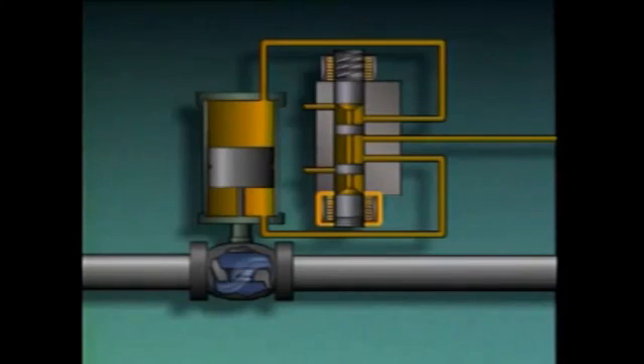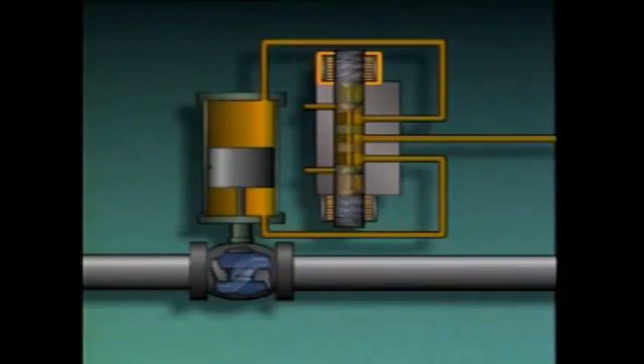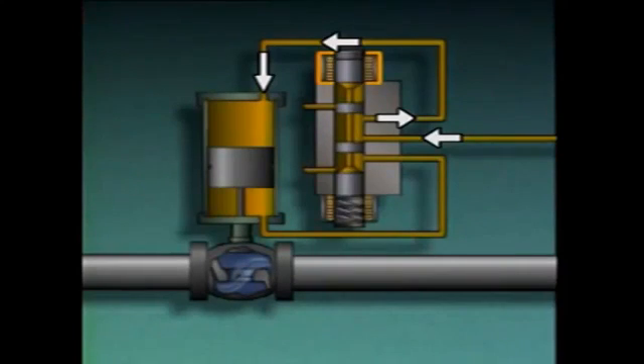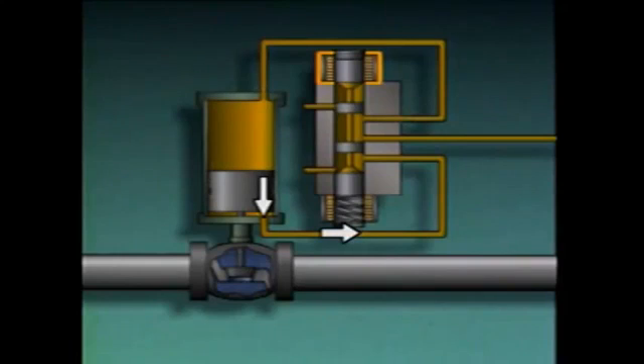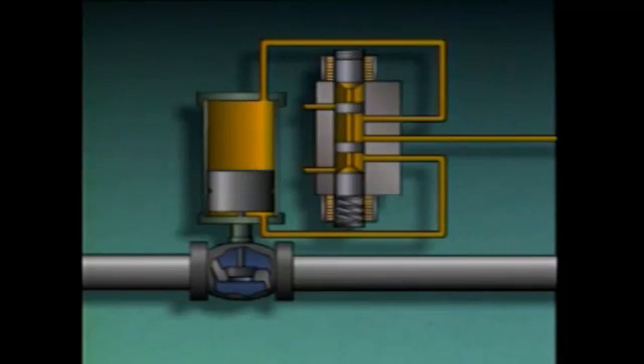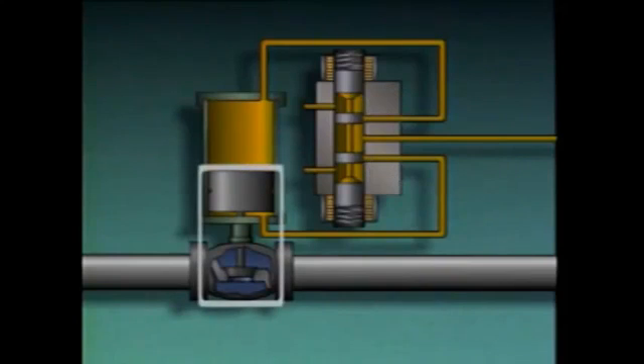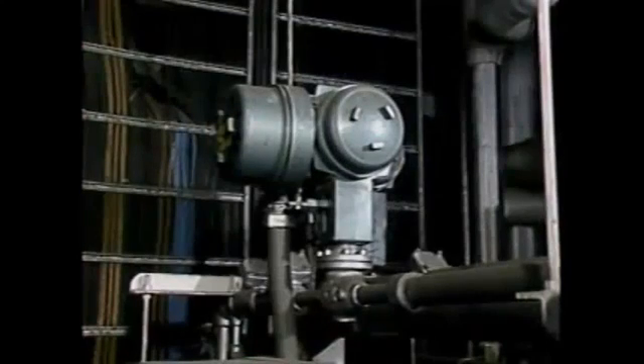The filling and venting of the actuator cylinder is reversed by de-energizing the lower solenoid and energizing the upper solenoid. When the upper solenoid is energized, it pulls the spool up, supplying hydraulic fluid to the top of the actuator cylinder, pushing the piston down and closing the valve. The fluid below the piston is vented back through the pilot valve to the hydraulic fluid supply. The piston can be held in place by de-energizing the upper solenoid, allowing the springs to return the spool to neutral and block the fluid lines. On a piping system diagram, a pilot valve is often represented by a specific symbol.